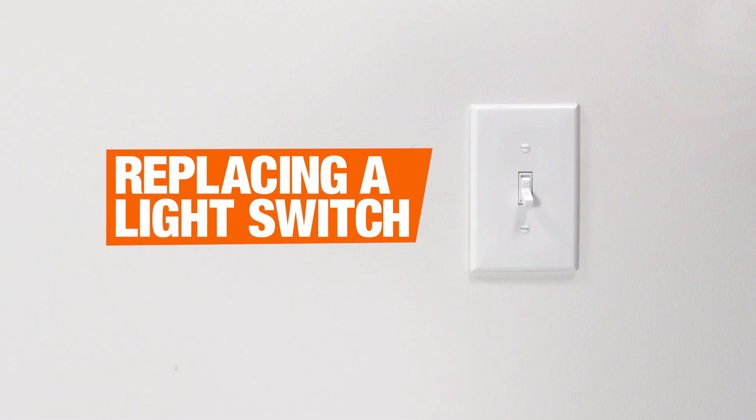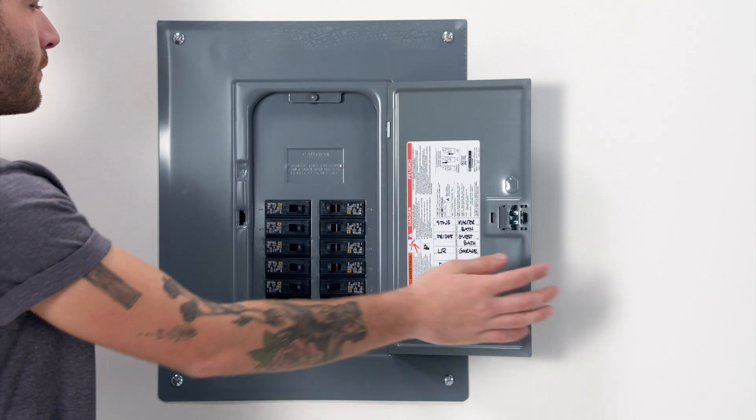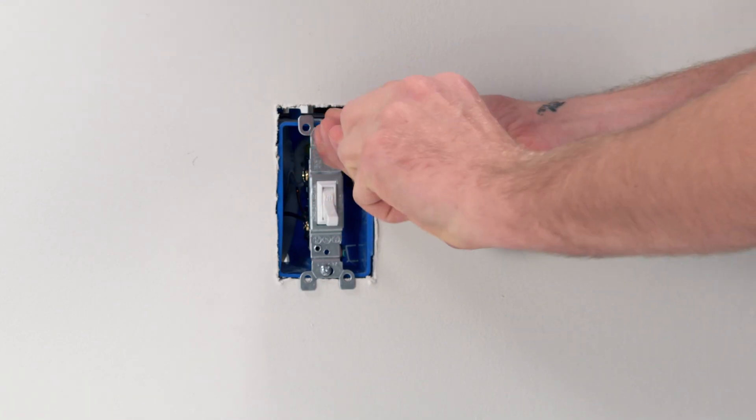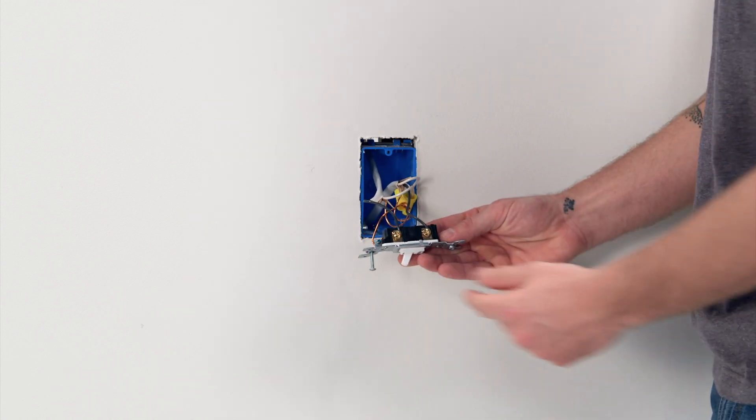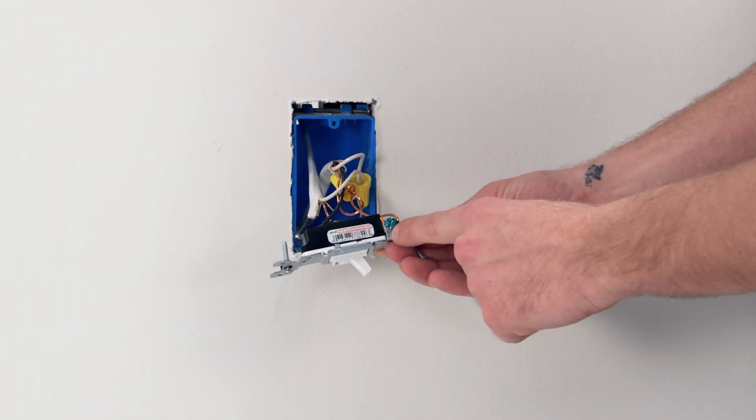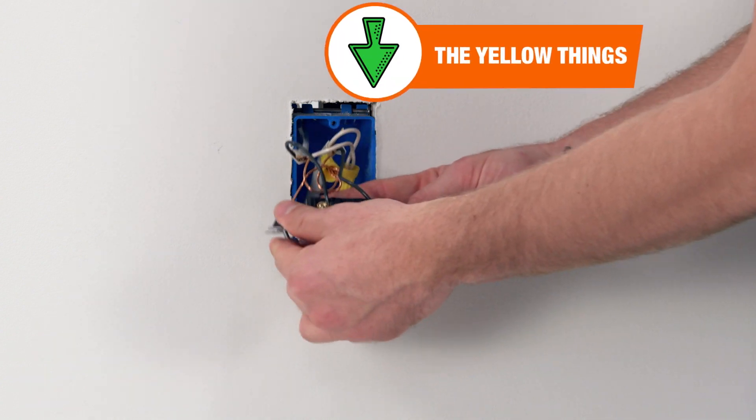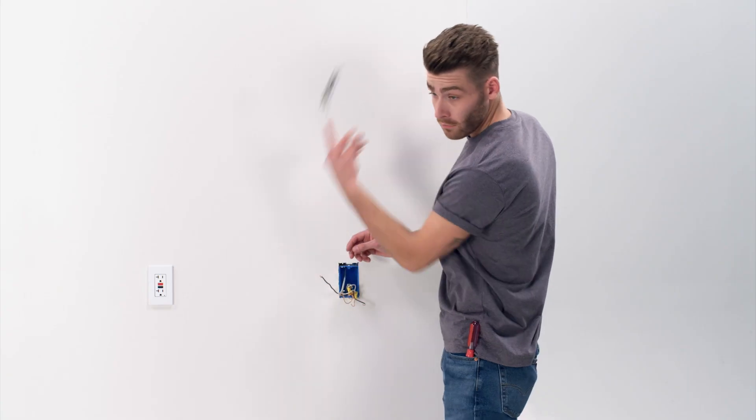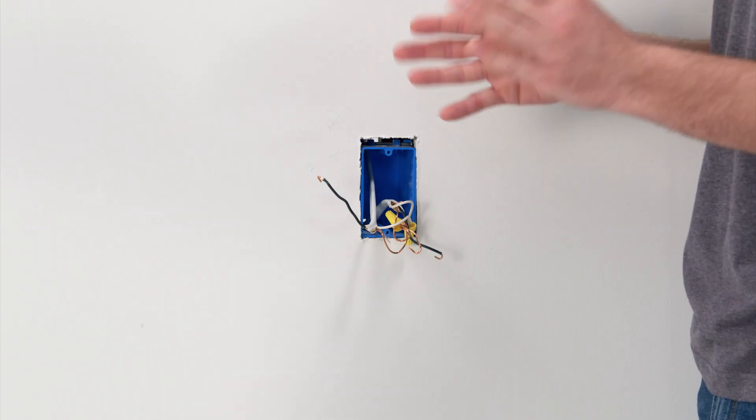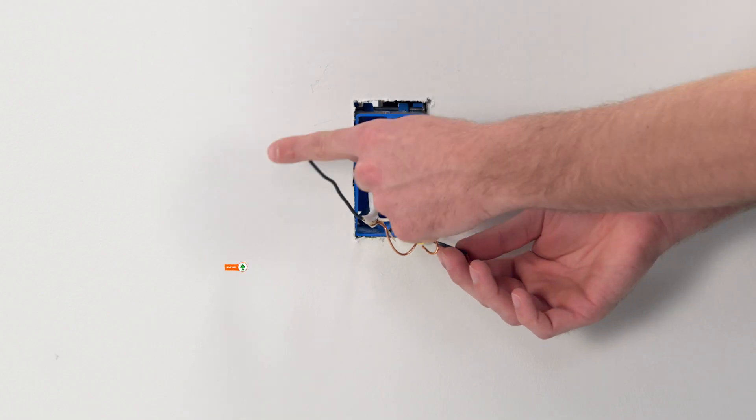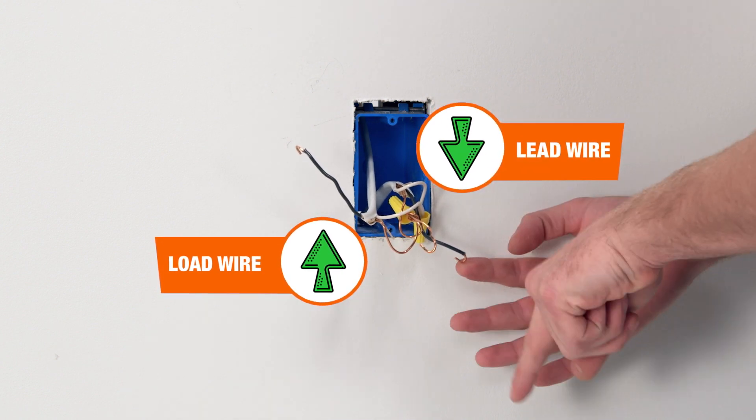Replacing a light switch to a dimmer is pretty much the same process. First, turn off the circuit breaker. And instead of connecting wires to the terminals on the side of your switch, we're going to be connecting matching wires to one another using cap nuts. For reference and to keep track of which is which, I've pointed my load wire up and my lead wire down.